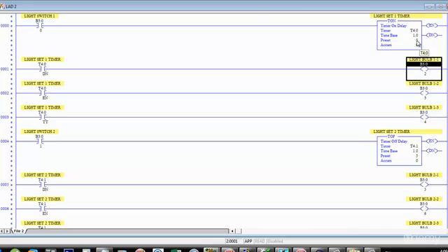This will stay down, this will stay energized, and this accumulator value will stay at 5 until one of 2 things happens. One, this condition becomes false, in other words, we turn our light switch off, or there is a reset, RES, command that we can use as an output on this timer, and it will reset the accumulator and start over again.